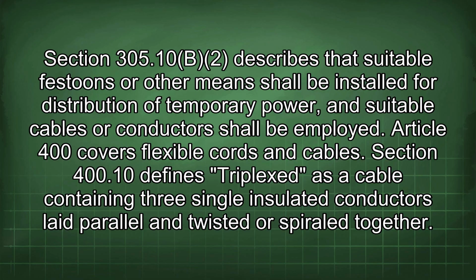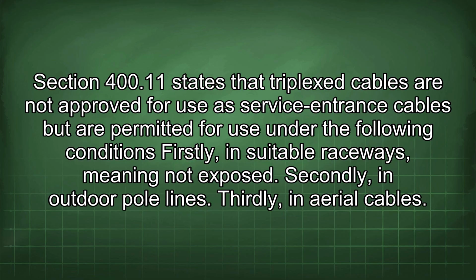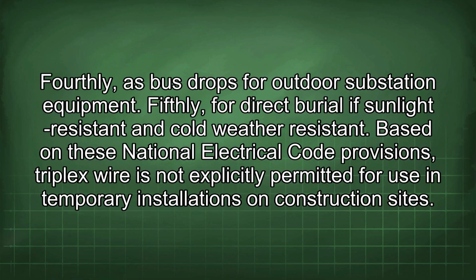Article 400 covers flexible cords and cables. Section 400.10 defines triplex as a cable containing 3 single insulated conductors laid parallel and twisted or spiraled together. Section 400.11 states that triplex cables are not approved for use as service entrance cables but are permitted for use under the following conditions: firstly, in suitable raceways, meaning not exposed; secondly, in outdoor pole lines; thirdly, in aerial cables; fourthly, as bus drops for outdoor substation equipment; fifthly, for direct burial if sunlight resistant and cold weather resistant.